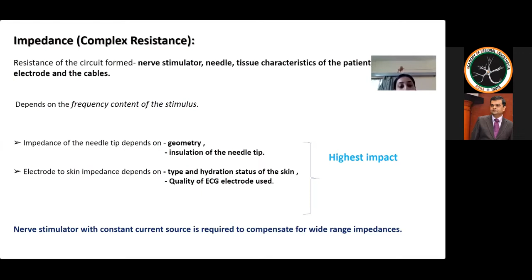ECG electrode. So the shorter the impulse used, higher will be the frequency content, and so lower will be the impedance. Whereas longer will be the impulse, lower will be the frequency content, and higher will be the impedance. That is the resistance of the circuit. So the nerve stimulator, by producing constant current, is required to compensate for the different resistance or the impedance produced by the circuit, which is done by increasing or decreasing the voltage.